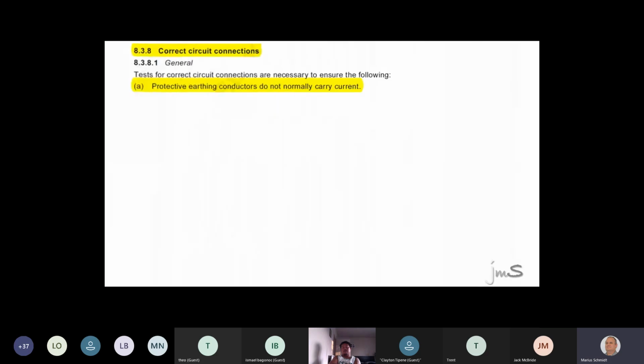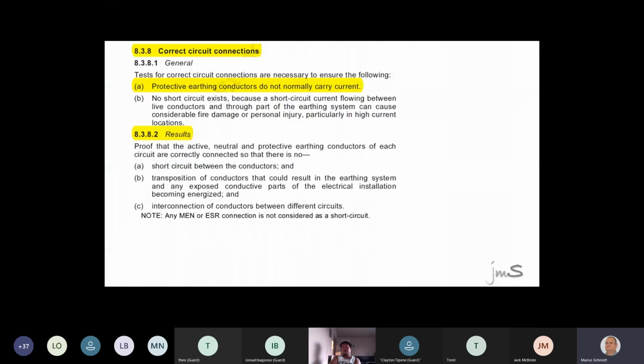Not much. If a circuit's correctly connected, your earth does not carry current. Your earth only carries fault current. Guys, another example. If your earth does not carry current, then the system will work. If earth carries current and you accidentally do something wrong, metal parts can become live. Now, it doesn't matter where you go, your earth is only carrying fault current, not operational current.